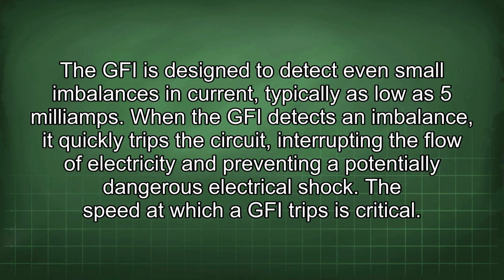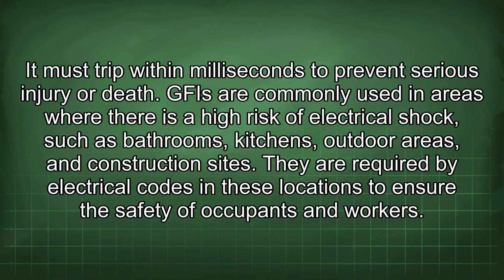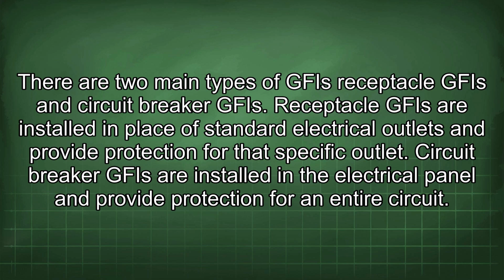The GFI is designed to detect even small imbalances in current, typically as low as 5 milliamps. When the GFI detects an imbalance, it quickly trips the circuit, interrupting the flow of electricity and preventing a potentially dangerous electrical shock. The speed at which a GFI trips is critical. It must trip within milliseconds to prevent serious injury or death. GFI are commonly used in areas where there is a high risk of electrical shock, such as bathrooms, kitchens, outdoor areas, and construction sites. They are required by electrical codes in these locations to ensure the safety of occupants and workers. There are two main types of GFI: receptacle GFI and circuit breaker GFI.